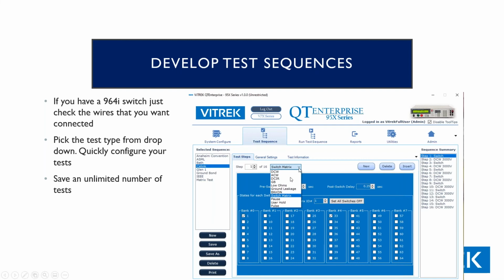After you pick the relays that are going to go on, you're going to select new, go to your next test step, and then you're going to probably do a DCW test. You're going to pick your voltage and limits and things like that, and then you're going to follow it up with another switch step where you would typically uncheck relay 1 and maybe check relay 2 or a corresponding relay over here on the low voltage side.